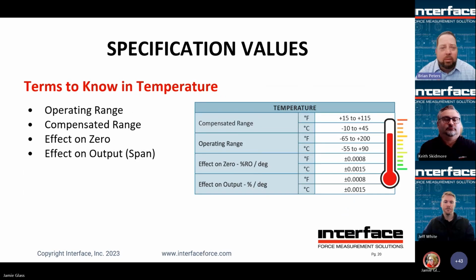All right, temperature. We're going to zoom in a little bit more here on temperature. It's important. I hope everyone comes away today with a better understanding of how temperature affects load cells, and this would be true for probably pressure sensors and other foil-based, or strain gauge-based, sensors, I should say. But there are a couple of parameters: one, operating range; two, compensated range; and then the effect on zero and effect on span. So next slide.